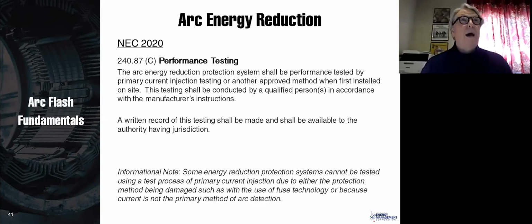So if you have a new switchboard, it arrives on site, it's got a circuit breaker with an ARMS switch on it, which we'll talk about in a minute. Code says you have to bring somebody in during initiation to do a primary current test on that thing to make sure that it works.